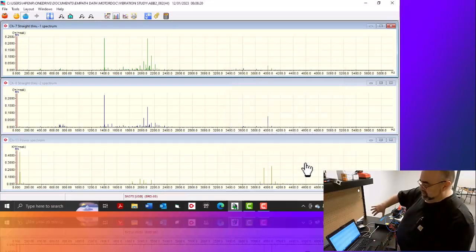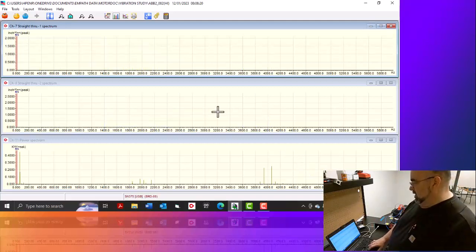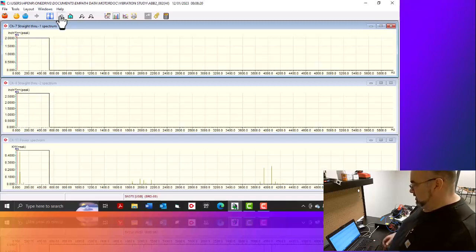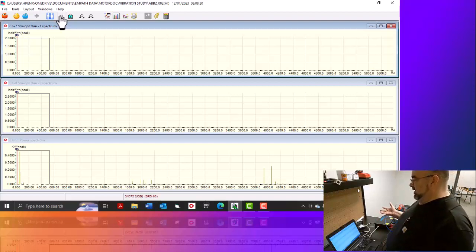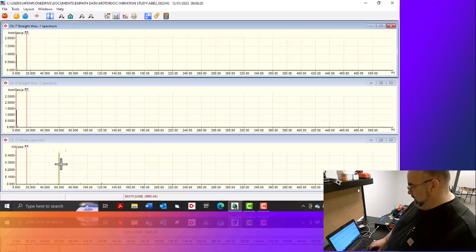That means this upper spectra here, all this stuff to the right, we're not going to be paying much attention to. So let's get down into an area of interest. Let's see what's going on, because it did say 1 time RPM, right? So it did say that there was some level of unbalance. So here's my running speed here. This is a line frequency peak. That's that harmonic content that's in the power spectrum. It's not showing up here, which is fine.